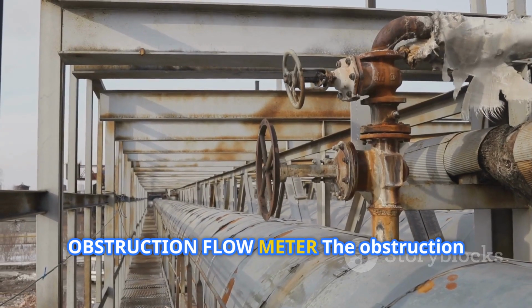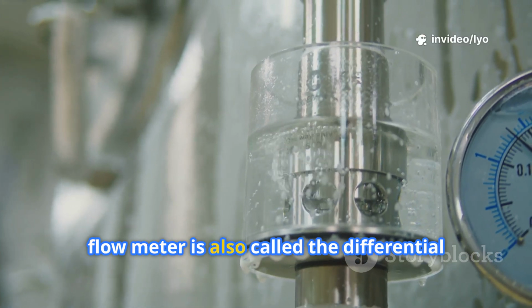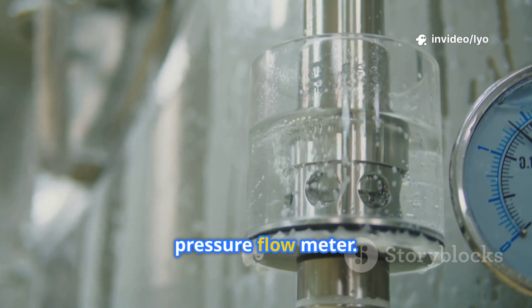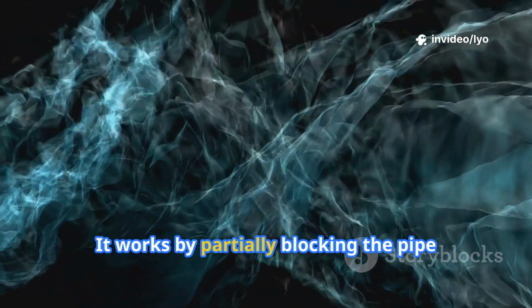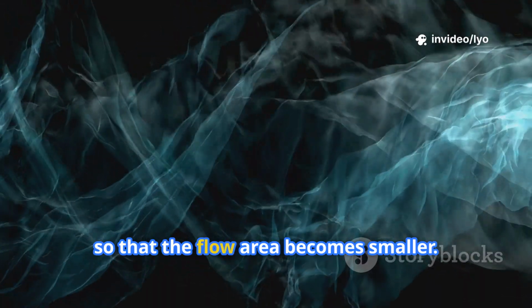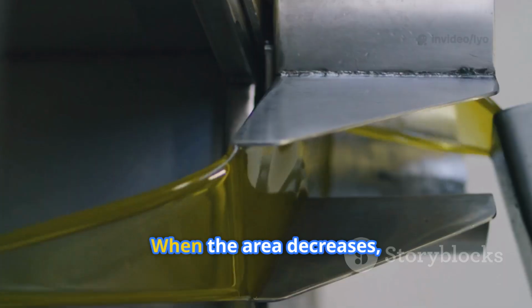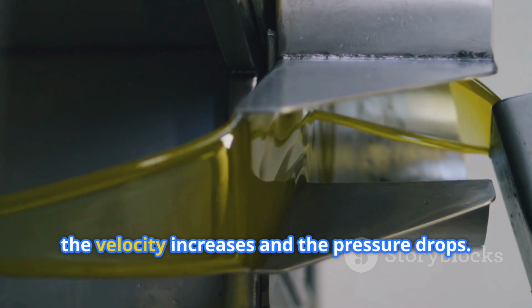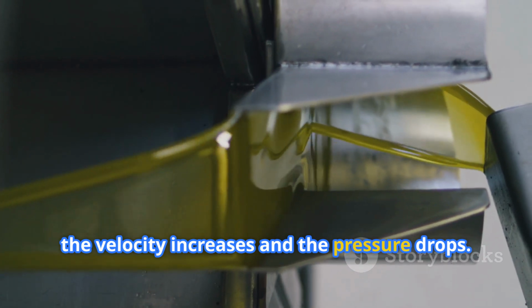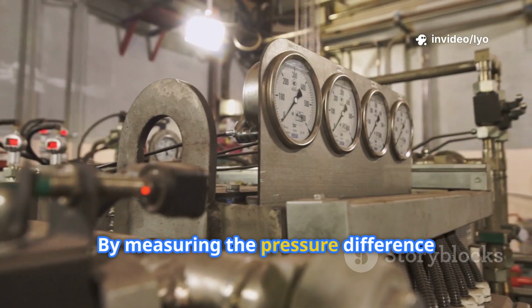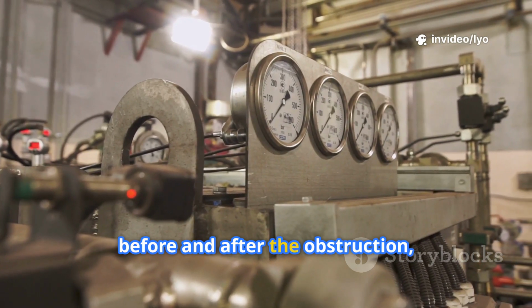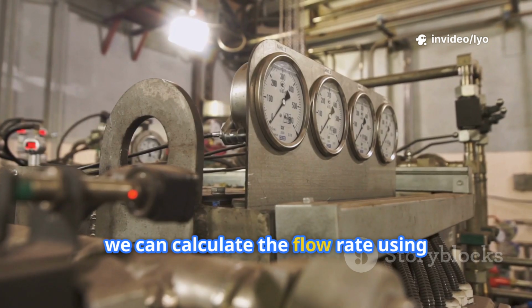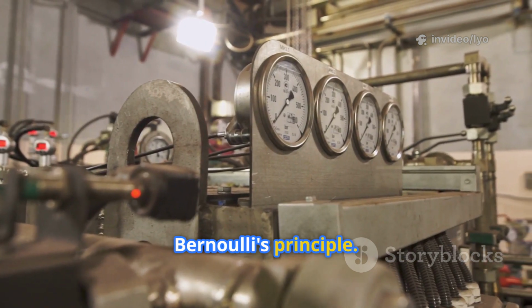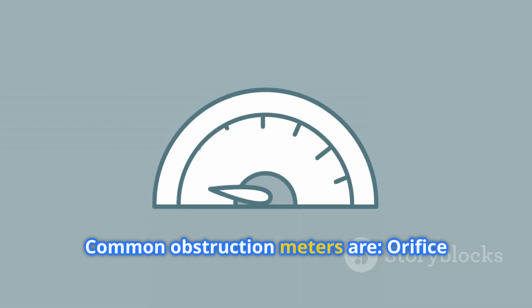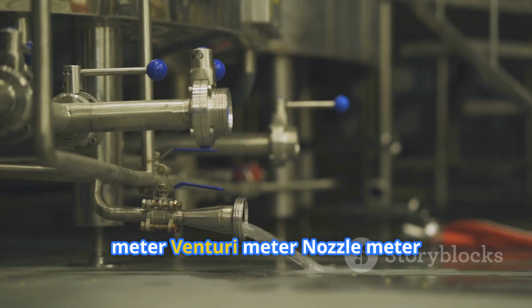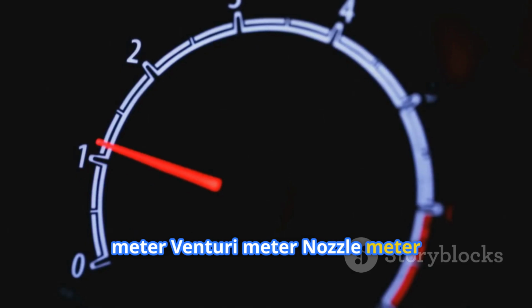Obstruction flow meter. The obstruction flow meter is also called the differential pressure flow meter. It works by partially blocking the pipe so that the flow area becomes smaller. When the area decreases, the velocity increases and the pressure drops. By measuring the pressure difference before and after the obstruction, we can calculate the flow rate using Bernoulli's principle. Common obstruction meters are Orifice Meter, Venturi Meter, and Nozzle Meter.